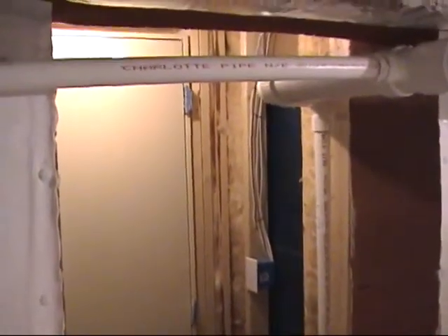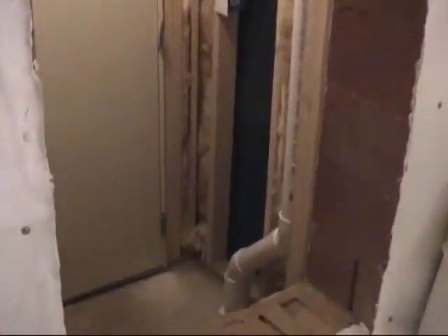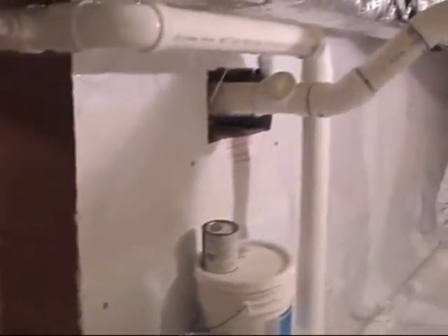So if the purpose is to control the humidity in here, you're not reaching the desired goal. Now part of that is due to the fact that there's a penetration right there. There's a decent sized access panel right there that goes into, like, an apartment.